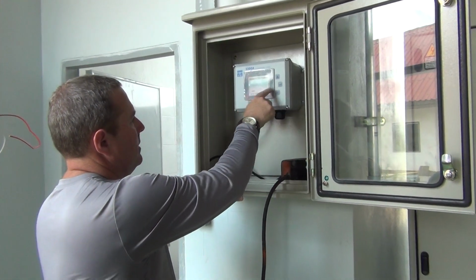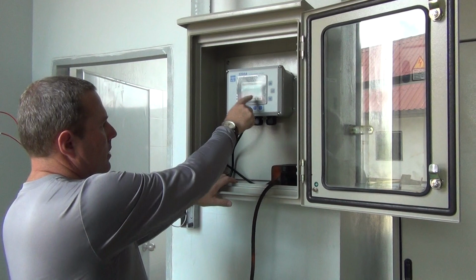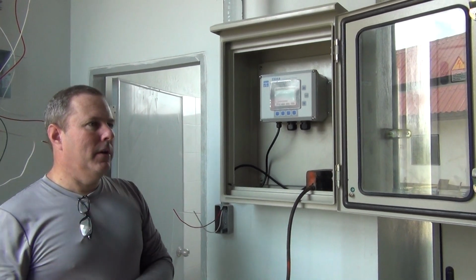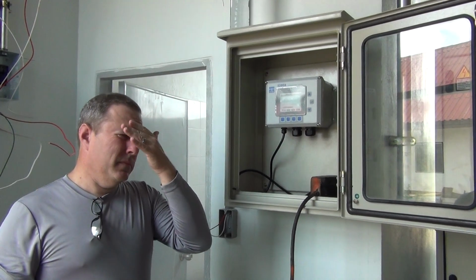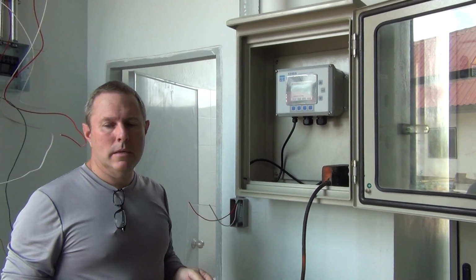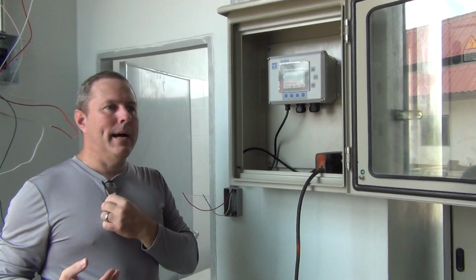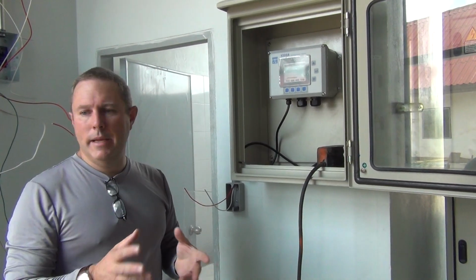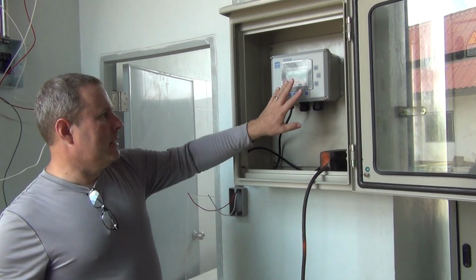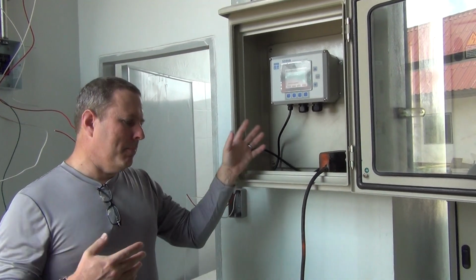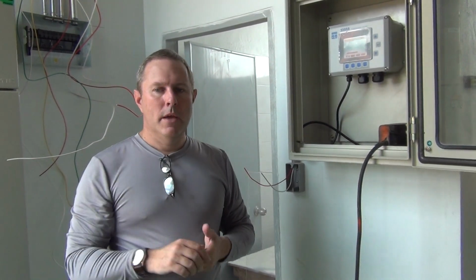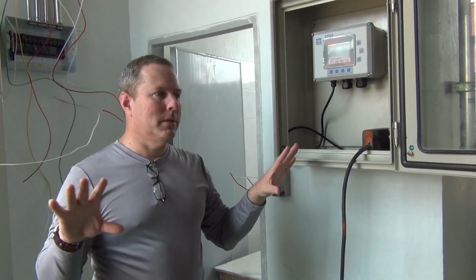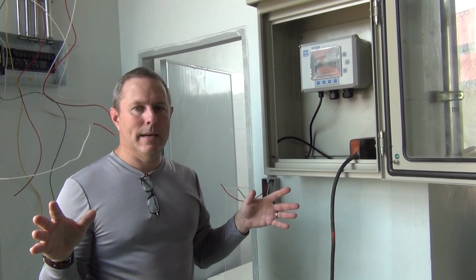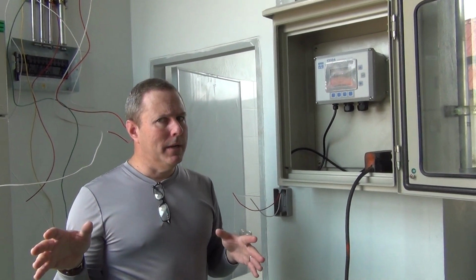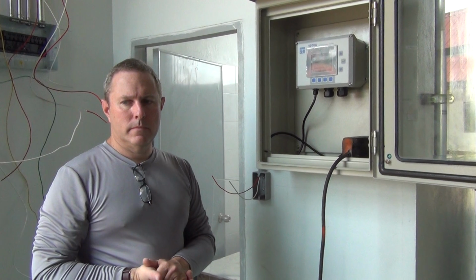Then, next, we have service hold disabled. If you are running high quality analytics, then you may be concerned about the data when you clean the probe or do maintenance. This is a function that can be enabled, that for example, when it's time to calibrate the probes or do some work on the system, you could push a service hold button and it will stop taking data for whatever your preset interval is. Is this something you need to worry about or not really? We do not have to worry about this.